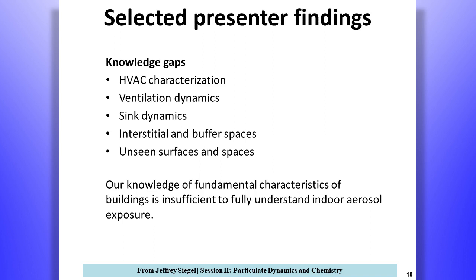That practical knowledge, however, is not very widely reflected in modeling, at least at this point, because a lot of indoor models are assuming there's a uniform mixing of airborne particulates when we know that isn't the case, and that uneven mixing is likely to be affecting exposure. Among the other gaps when it comes to understanding particle size dynamics in indoor concentrations are the characteristics of the heating, ventilation, and air conditioning system, the dynamics of ventilation, that is the air exchange rate and how that changes over time. The dynamics of the various sinks, not just the wall, the floors, carpeting, and the like, but filter efficiency for filters in the HVAC system.